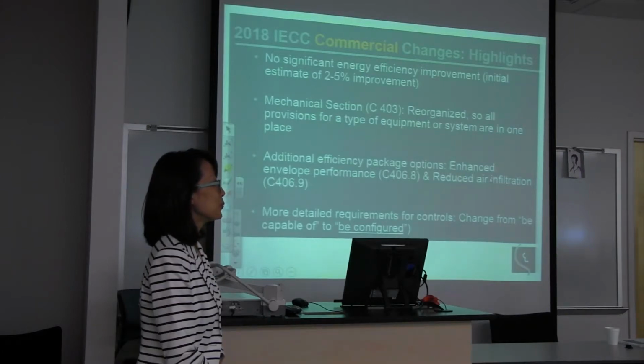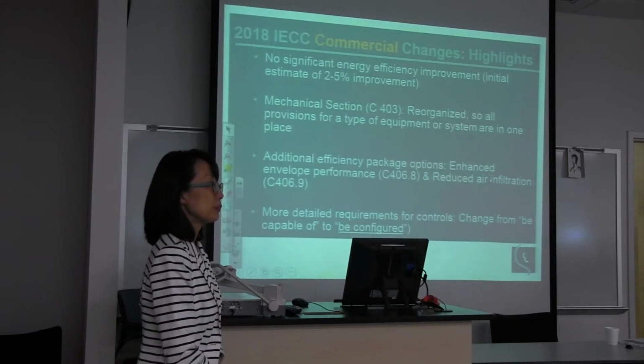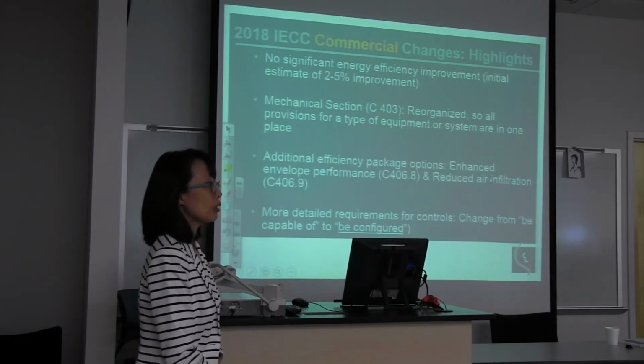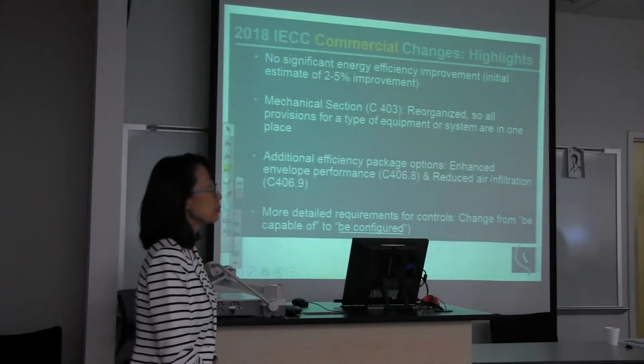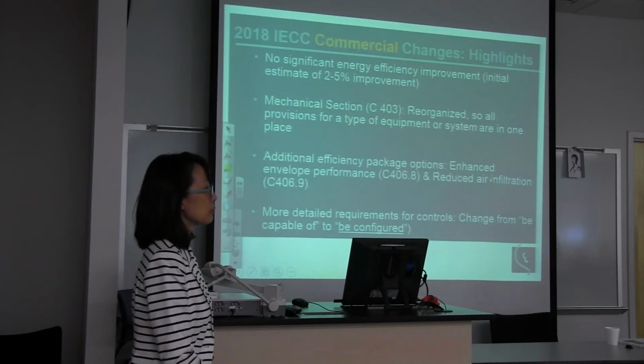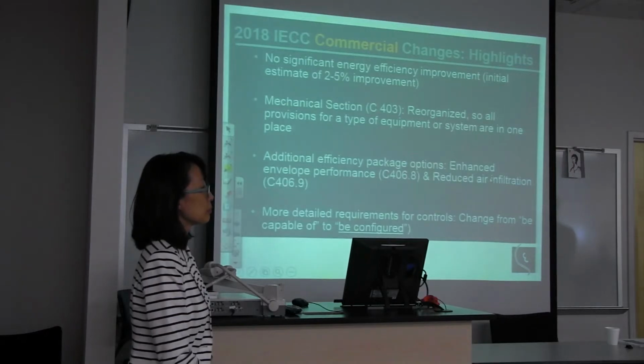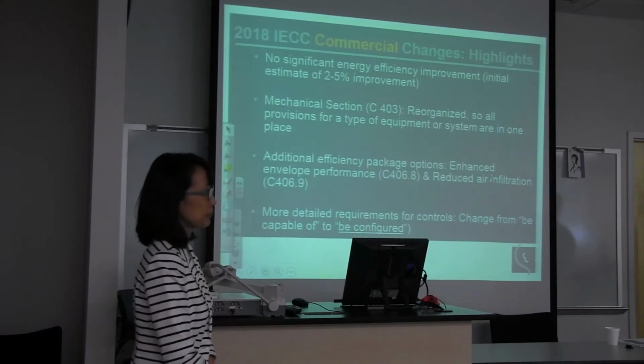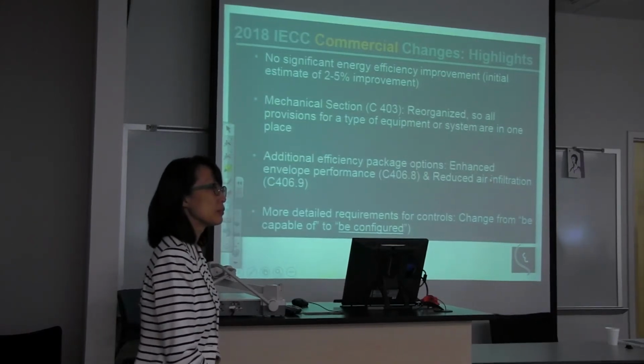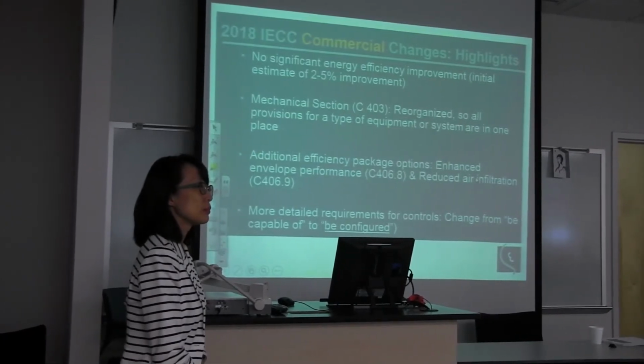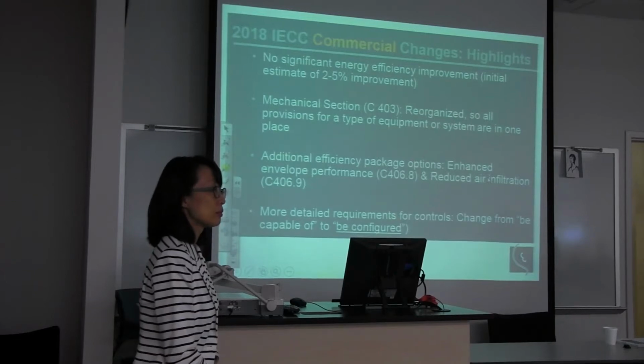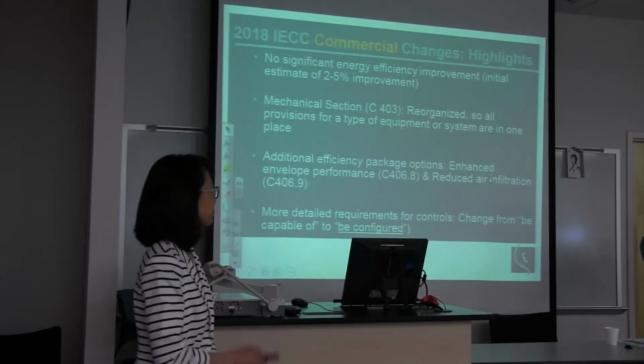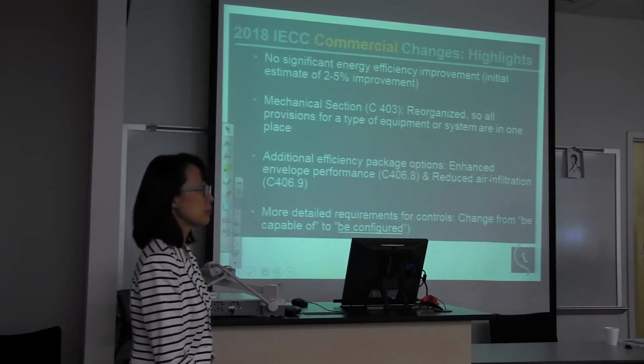That goes back to the definition of what is conditioned. IECC does have a classification for unconditioned, which doesn't exceed a certain threshold - it's called low energy building. It seems ASHRAE is more flexible on getting to unconditioned, with an easier number to meet. ASHRAE has that semi-heated category, which falls between unconditioned and conditioned. IECC does define a non-conditioned area but allows for a little bit, like 3.4 BTU. IECC has only one cutoff point where ASHRAE has two, so if you fall in that middle spot, you might see ASHRAE compliance used instead.